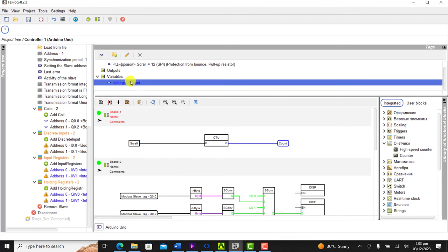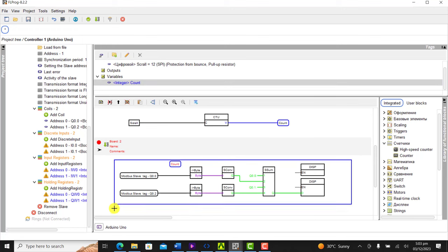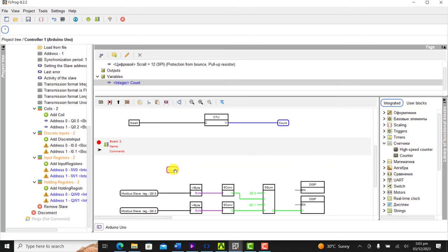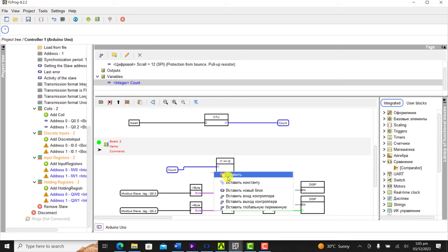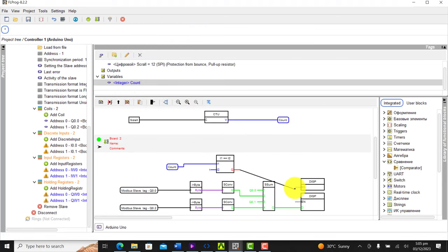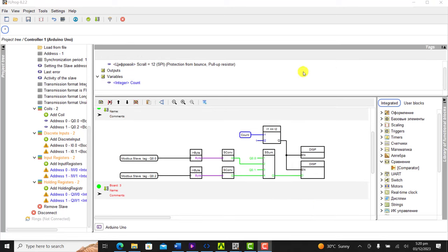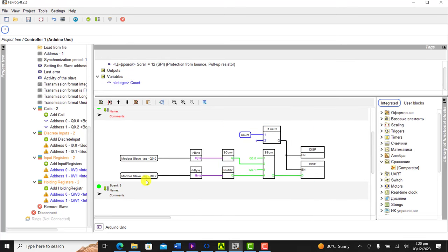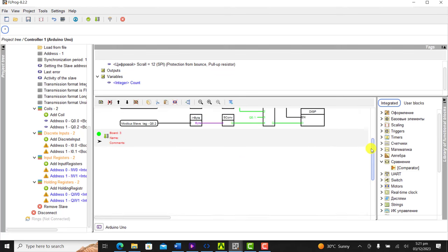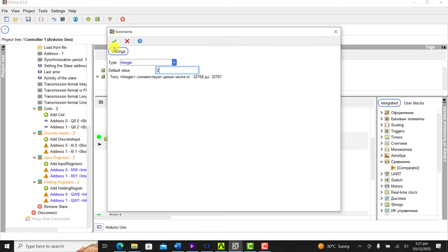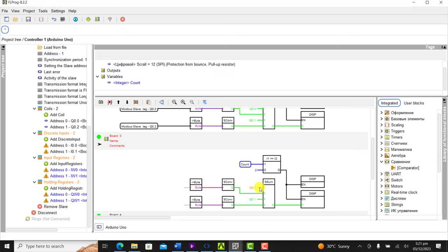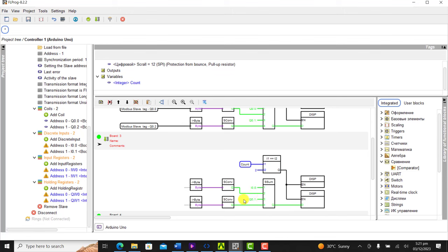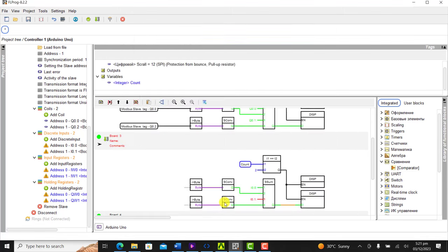We drag our count variable to our second board, and then we need a comparator. We wire the counter to the first input of the comparator and give it a fixed number 1 to the second input. Wire the output to our display values. Then copy this portion to the second row, which is going to form the display of our discrete inputs. We change it to 2. We now change the constant display value to input register. We change this portion to I0.0 and then this section as well to I0.1.